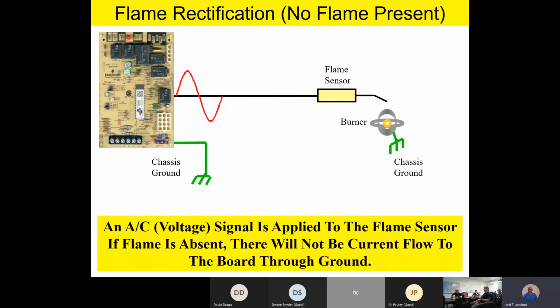As a quick review, remember, team, anytime you have power to the board, we're going to be putting 115 volt to the flame sensor. Now, it should be noted this voltage, even though it's line voltage driven to the flame sensor, it's not going to shock you. It's not going to hurt you. It's not going to burn anything up if it shorts the ground, because it's an extremely high resistance circuit.